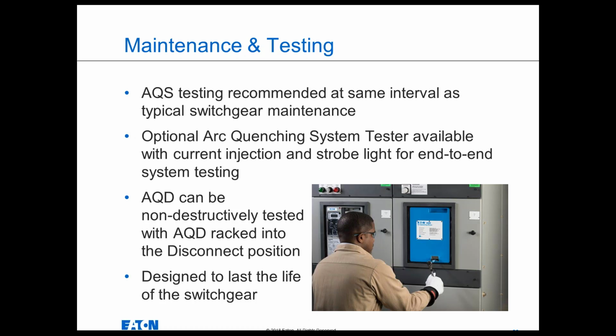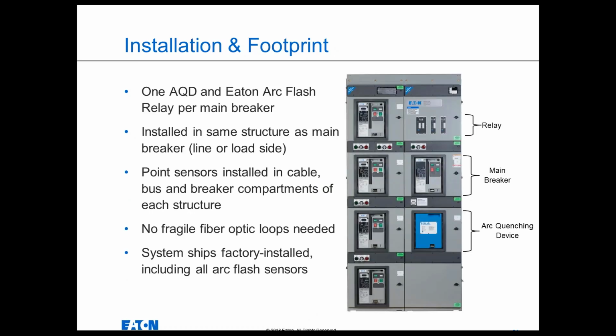So the entire system monitors itself from end to end and will notify you of a problem, but it also, for peace of mind, can be tested from end to end. In terms of installation and footprint, what's required is one Arc Quenching device and one set of relays per main breaker. So if you have the main-tie-main lineup and the ties open, you're essentially operating two independent lineups potentially. So that's what drives that. You've got to be able to quench an arcing fault on bus A or bus B.